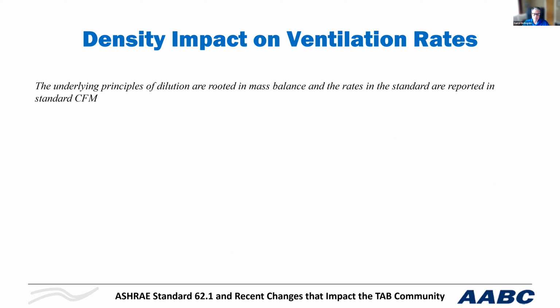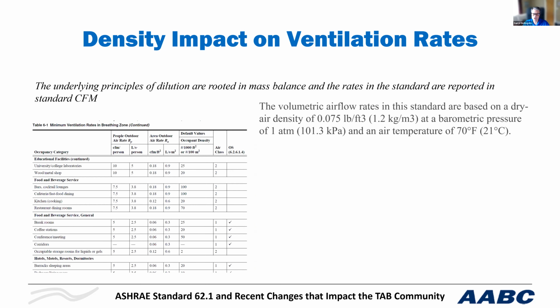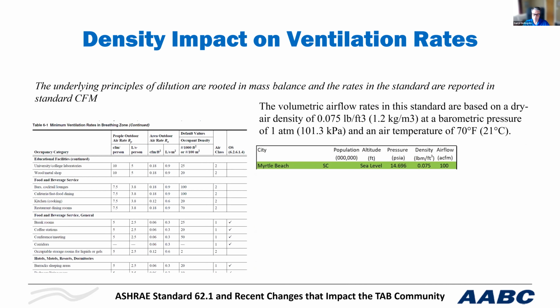Density impacts ventilation because ventilation's purpose is to dilute, and the way it dilutes is with a mass volume of air. Density impacts this mass volume. The ventilation rate procedure table in ASHRAE Standard 62, Table 6.1, is based on mass airflow at standard conditions that are listed here. So if you take this table and apply it, for example, to Myrtle Beach, it applies well because it's at sea level and at 1 atmosphere, assuming the same temperature.